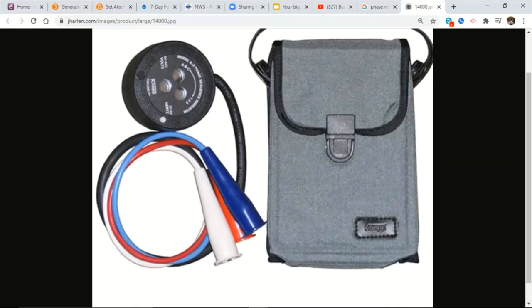If I put it in brand new and mark it clockwise, ABC, if something fails in the future and I need to change that transformer out for any reason, I need to match whatever was there in the beginning. So it's pretty much imperative that on any new three-phase installation, you mark the phasing letters and the rotation direction.